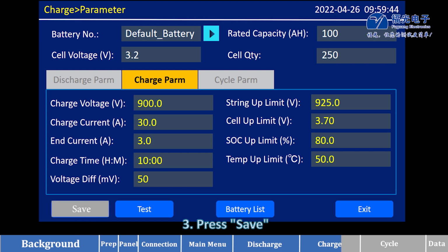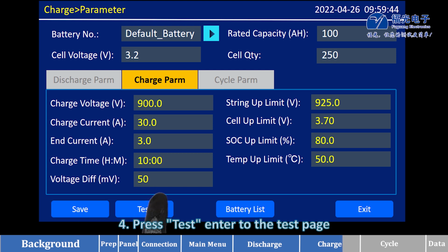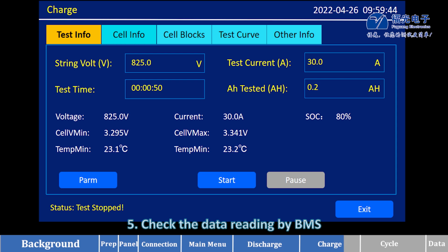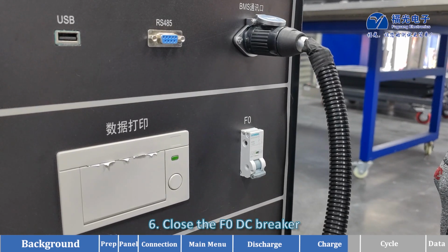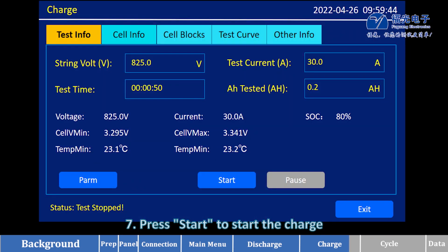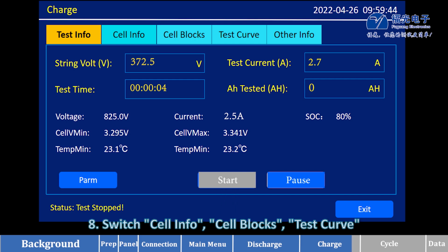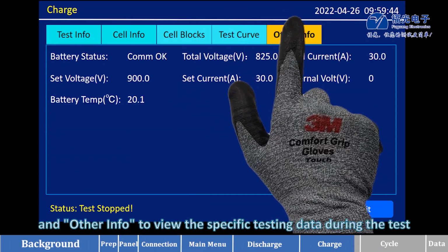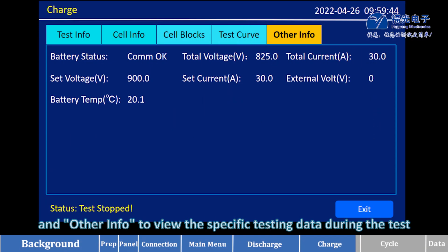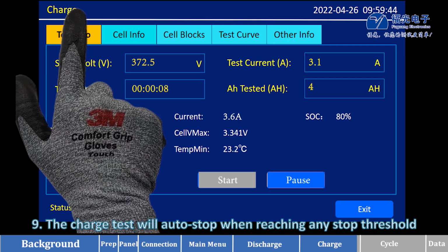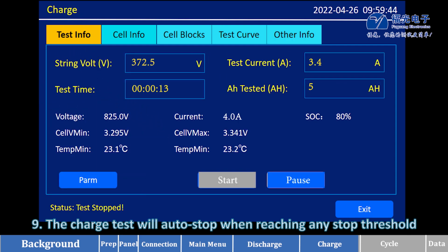Third, press save. Fourth, press test enter to the test page. Fifth, check the data reading by BMS. Sixth, close the F0 DC breaker. Seventh, press start to start the charge. Eighth, switch cell info, cell blocks, test curve, and other info to view the specific testing data during the test. Ninth, the charge test will auto-stop when reaching any stop threshold.